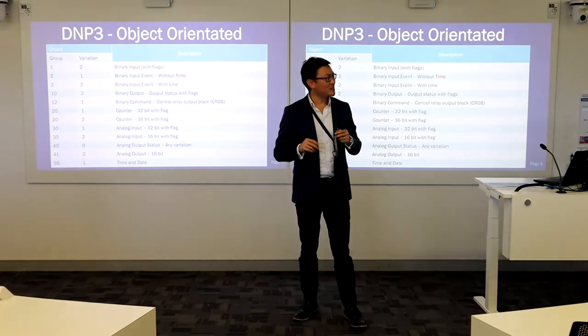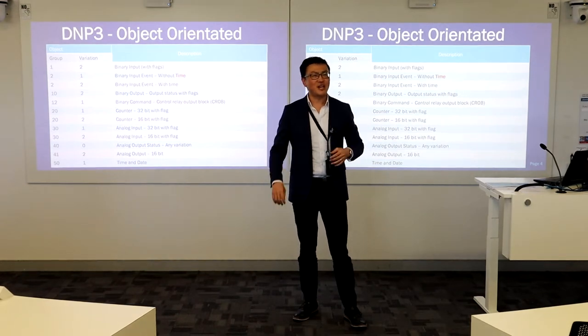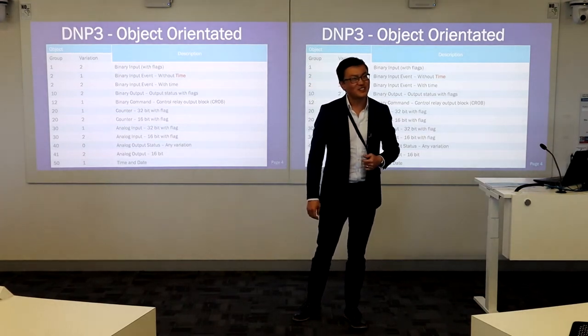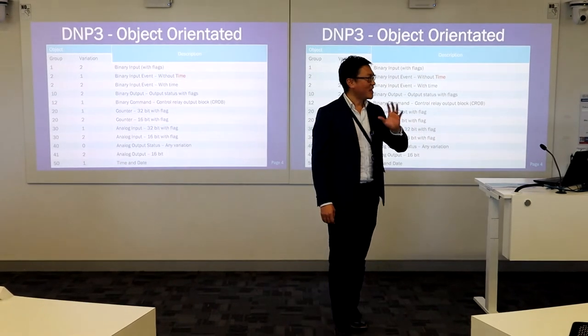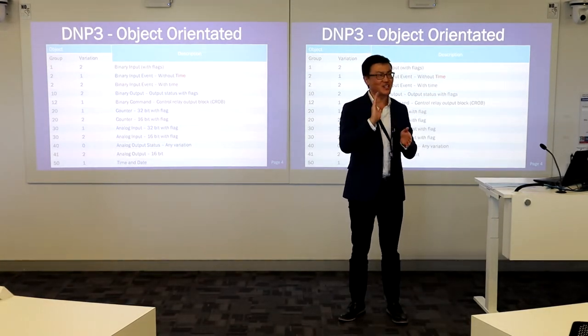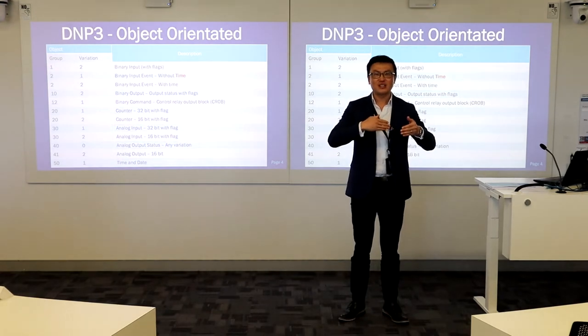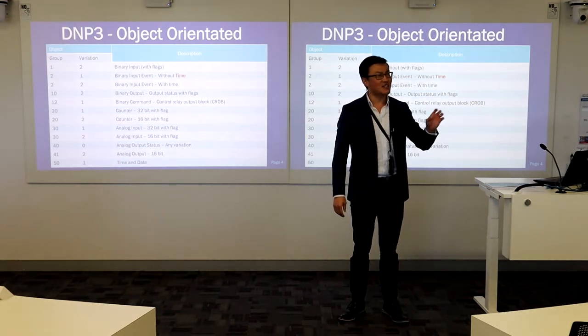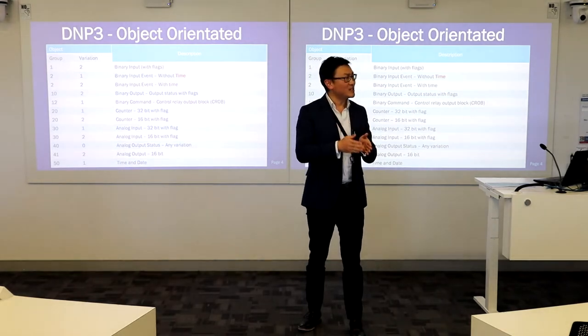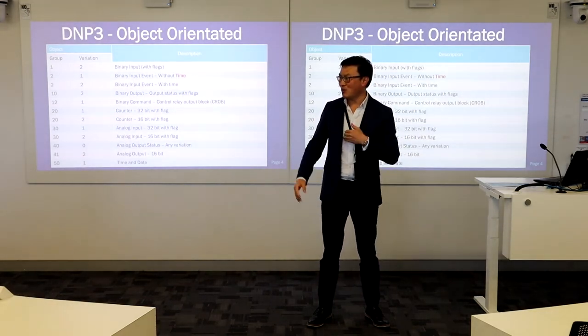Why do I use the words 'work out'? It's not just accepting. The local DNP3 RTU needs to work out the local time because there is a time delay to different locations and different transmission nodes. The slave cannot passively accept the time because then the time will be wrong. It may take one second for the message to arrive at any slave, creating a discrepancy in data integrity. The SCADA server will work out the time delay — based on measurement, it knows the one-second delay, so it sends the time and the slave can add that offset on top.